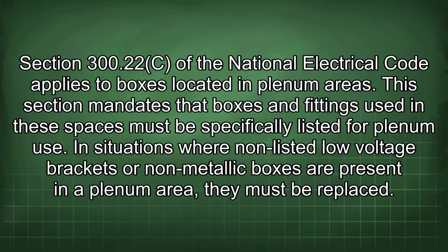Section 300.22c of the National Electrical Code applies to boxes located in plenum areas. This section mandates that boxes and fittings used in these spaces must be specifically listed for plenum use. In situations where non-listed low-voltage brackets or non-metallic boxes are present in a plenum area, they must be replaced.